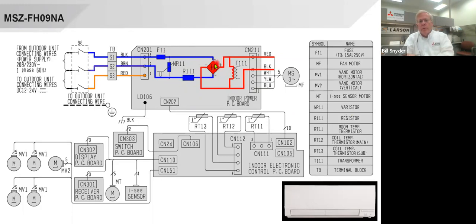Here's where we convert from AC to DC, and you can see plus and minus. And we go out to the main fan motor here, MS. Is that labeled here? Doesn't say it, but that's the main fan. Down here, you're going to see these are DC motors. There's 4 of them. These are all vane motors. All 5 of these are vane motors. Some of them are, as you'll see, horizontal vane motors and vertical vane motors.